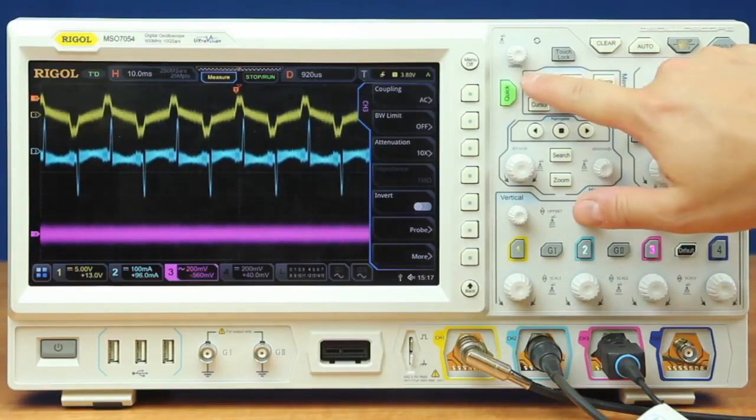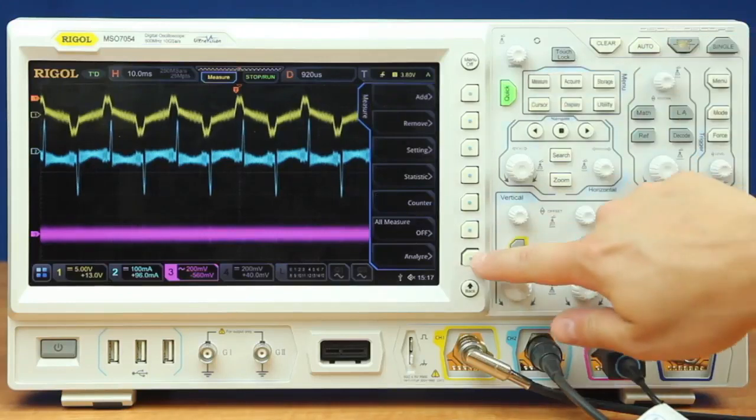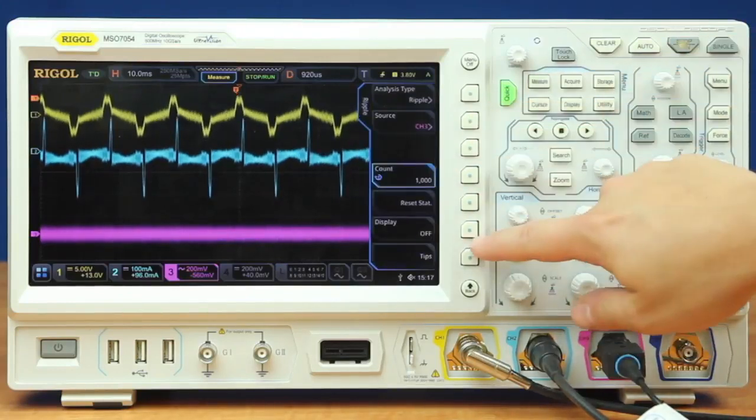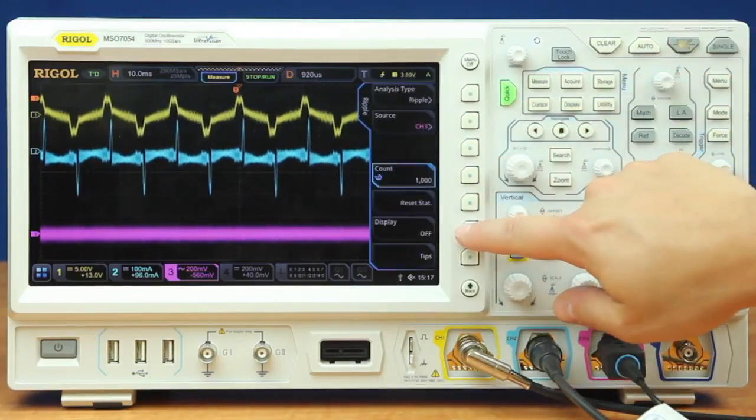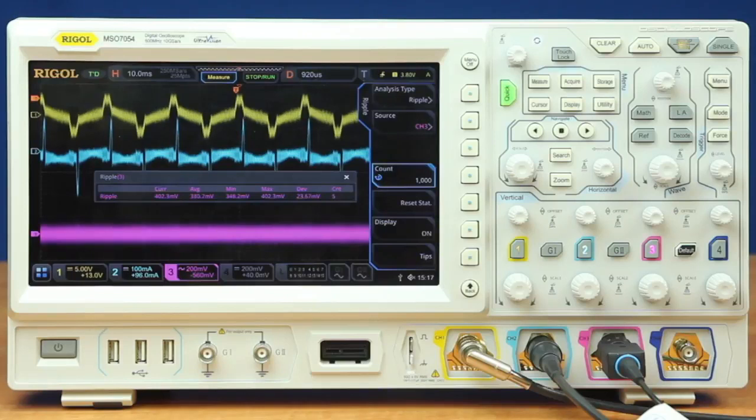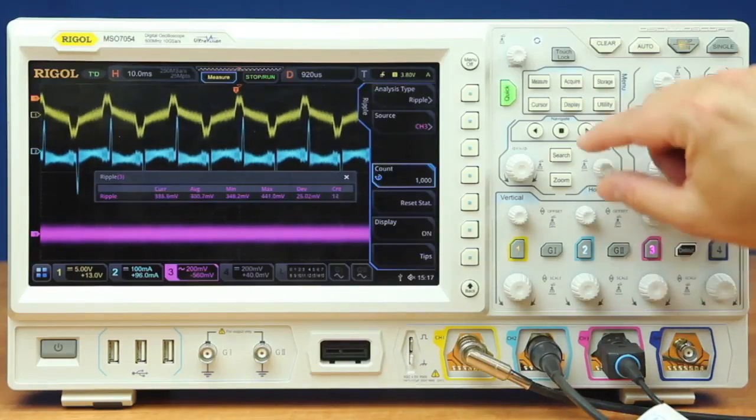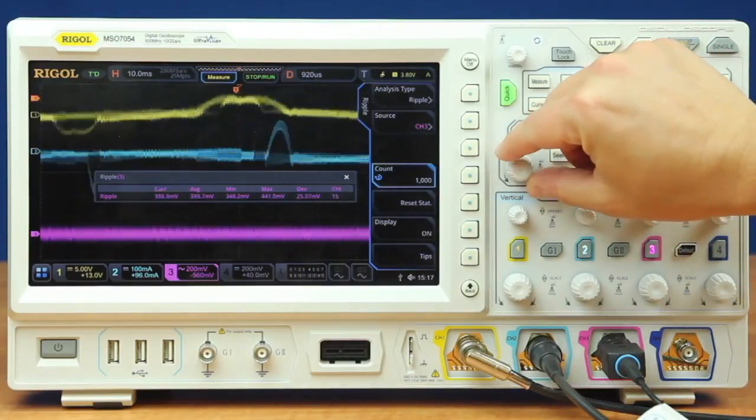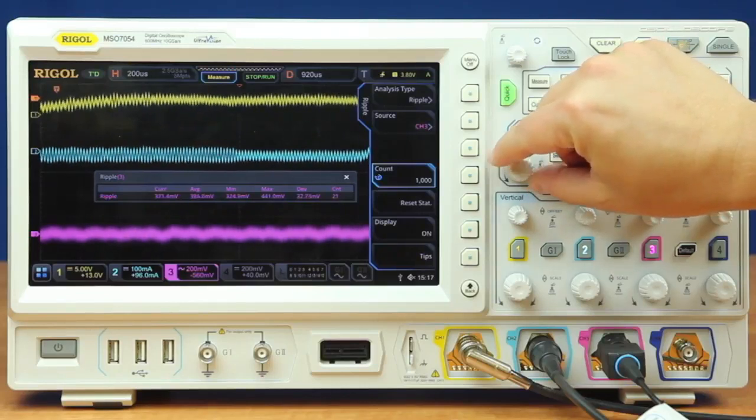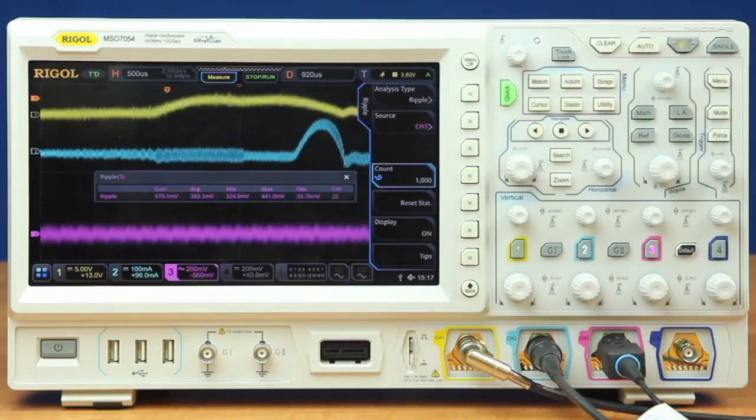Now we can go ahead and go into our power analyzer. We can turn that power ripple display on so we can measure the ripple. We can also if we want zoom in and see the frequency of that ripple a little better.